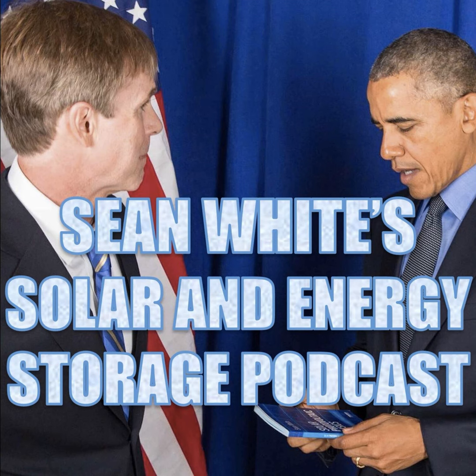The MID that's not as a service, so it's just handling a feeder. This is probably the most common way that Tesla Powerwalls and things like that are being installed today, rather than a whole house backup. But there are a lot of whole house backups where now the gateway or whatever, the microgrid interconnect device, is put in as the service point. All the service flows through that.